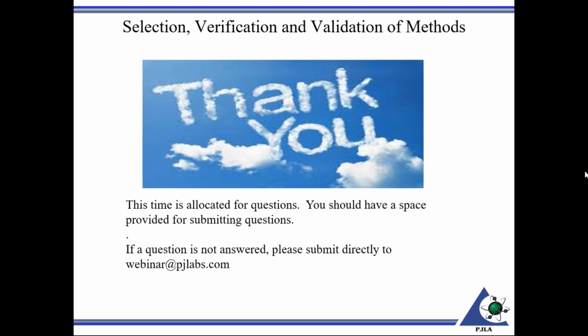And like I mentioned, calibration is not a one-time thing, and risk would need to be taken into consideration. If you have something set on an annual basis, I would recommend, if you felt the need and you considered risk, where you need to extend it for another, say, a month based on the availability of your particular supplier, that you document that you've extended the calibration interval, considered the risk, i.e. that it would have gone out of tolerance, and document that.